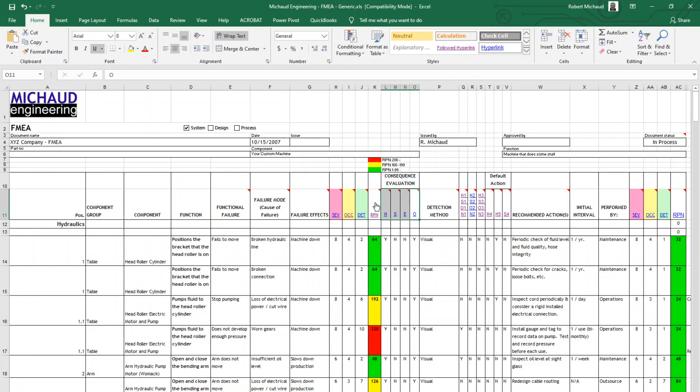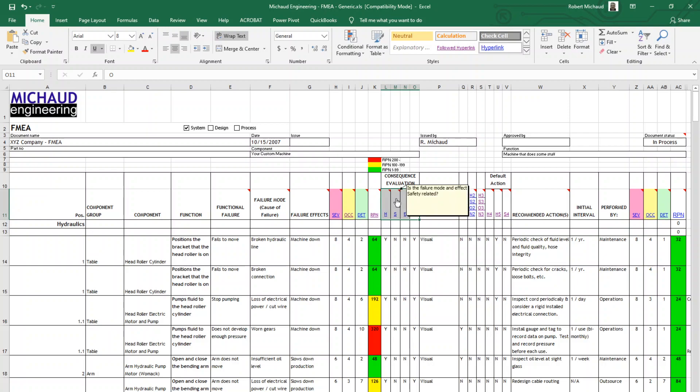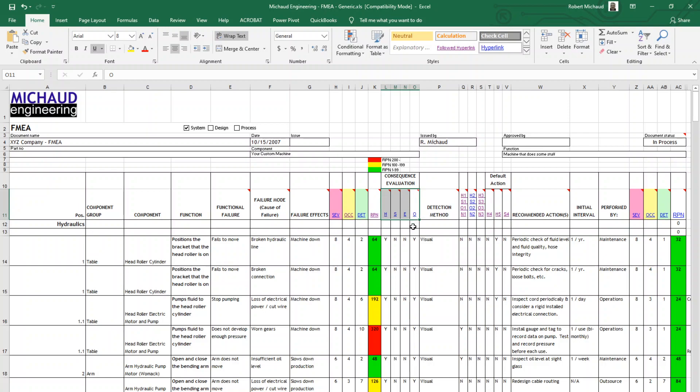Next, we're going to look at the consequence evaluation. In each of these categories, we're going to ask the team the following questions. Is the failure mode and effect hidden? In other words, can it be readily detected? Yes or no. Next, is the failure mode and effect safety related? This is important, obviously, for safety reasons. The third one is for environmental impacts. Will the failure mode have an environmental impact? And lastly, will the failure affect operations? Each one of these gets a yes or no answer.